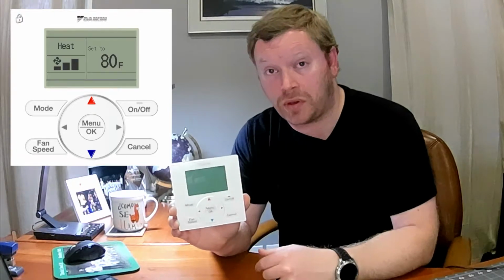Within the NAV controller, there's your heat set point and your cool set point, and it's important that you know which one you're changing, because when you walk up to the NAV controller and it says heat at the top, the set point that's displayed is the heat set point. So many times we'll have people call in and they'll say, hey, I keep lowering the set point, but the cooling won't come on, or I keep increasing the set point, but the heat won't come on. And it's important to note that when you're changing your set point, you're only changing the active set point. So if it says heat on the NAV controller, that means you're changing the heat set point.